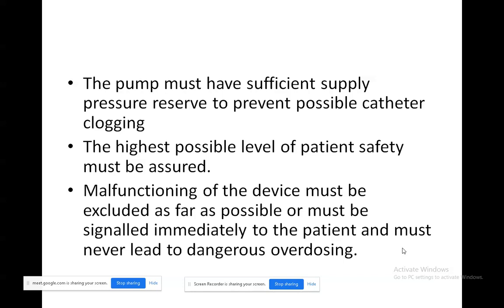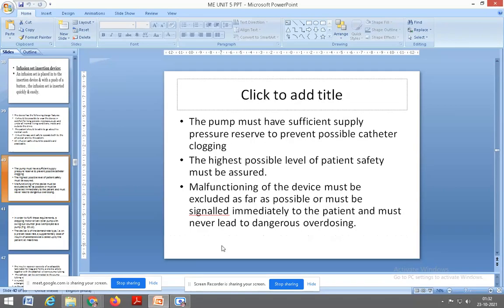And then malfunctioning of the device must be excluded as far as possible, or must be signaled immediately to the patient and must never lead to dangerous overdosing. So we have to use the device properly, that is, periodically, so overdose is avoided. You have to set the proper dose level as well as the periodic timing. So in the interval, only this much dose should be given. You should not give the insulin dose too often. Okay.